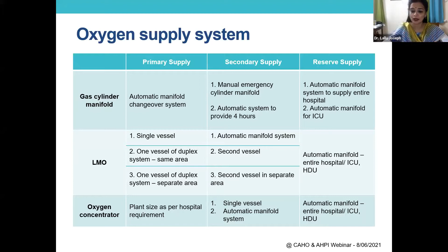So this is extremely important. And if you have an oxygen concentrator, that becomes your primary supply. And then you can have a single vessel LMO as your backup, or an automatic manifold system as a backup. Reserve supply, again a manifold, or just your ICU or HDU covered. So this table is very important. You can't just say I have one system and do away with that one system.